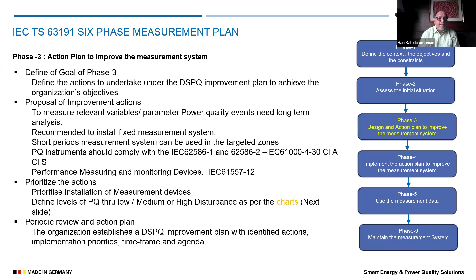The fourth action is the installation action. We need to ensure the implementation of this process, that is, wherever we want, how do we put the meters, which device we need to put, and all that. We need to start the implementation action, like whether we have proper CTs, whether the CTs are properly configured with reasonable accuracy we can use, or whether we have to buy a new CT, or we cannot install a CT in that place because the panel has a smaller area. Probably we can use alternative methodologies, we need to look at this in this particular phase.